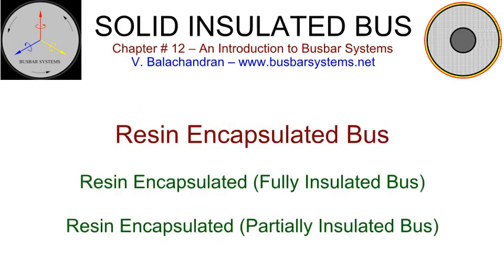Resin encapsulated bus. Resin encapsulated bus are designed to be installed in a system with a rated voltage up to 36 kV. They are ideally suited for indoor installations in switchgear rooms and outdoor installation in switchyards, interconnecting transformers and panels. A tubular conductor is pre-formed and encapsulated in resin along its entire length for the desired insulation level. The resin encapsulation process is carried out under vacuum and cured to remove any remnant stresses. A corrugated polyamide outer sheath of adequate thickness covers the entire length of the cast conductor for protection against moisture, ultraviolet radiation, and direct rain.